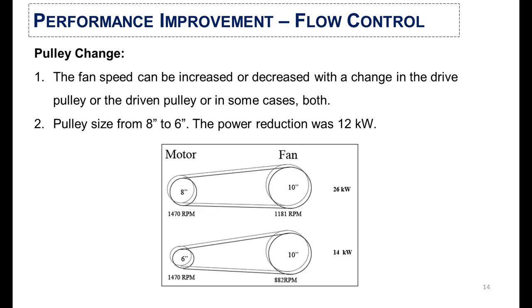The pulley change has a very significant impact. If we increase or decrease the diameter of the pulley on the driver or driven side, it directly impacts the flow of the blower or fan. In this case, you can see that when the pulley size is changed from 8 to 6 inches, we saved 12 kilowatts of power.